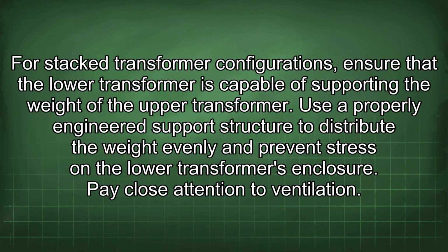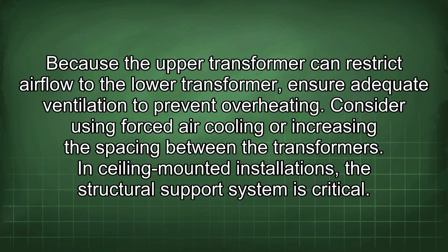For stacked transformer configurations, ensure that the lower transformer is capable of supporting the weight of the upper transformer. Use a properly engineered support structure to distribute the weight evenly and prevent stress on the lower transformer's enclosure. Pay close attention to ventilation. Because the upper transformer can restrict airflow to the lower transformer, ensure adequate ventilation to prevent overheating. Consider using forced air cooling or increasing the spacing between the transformers.